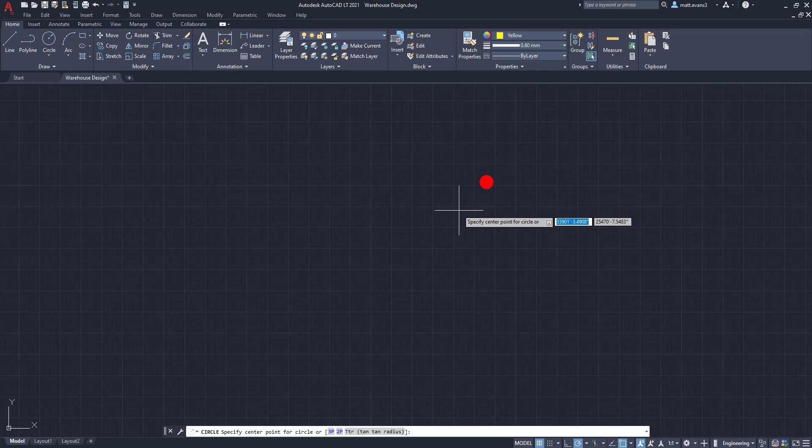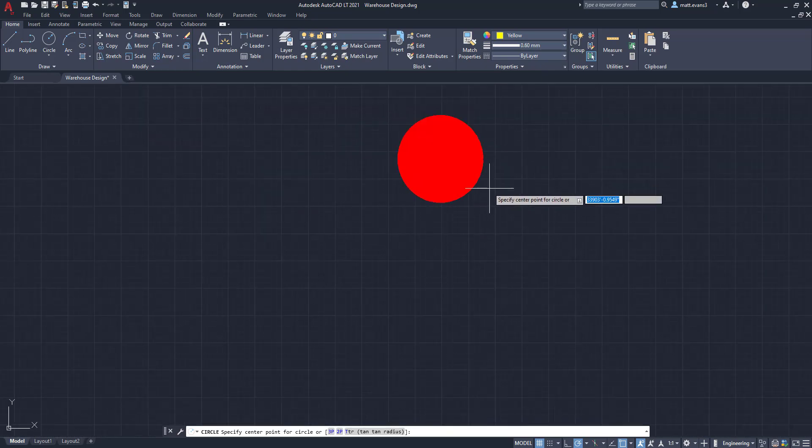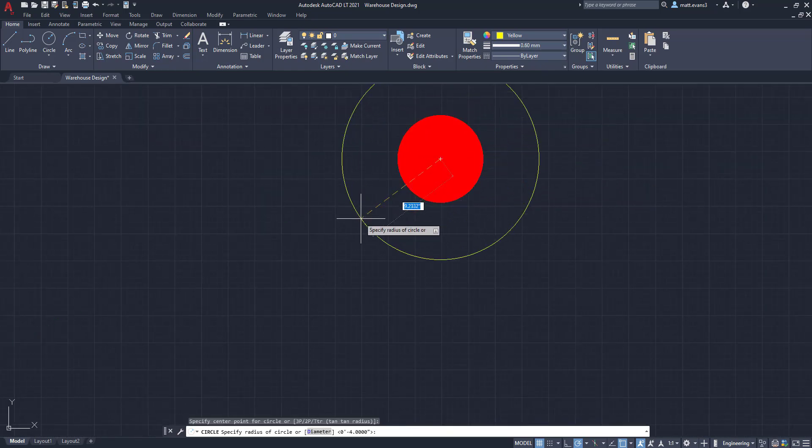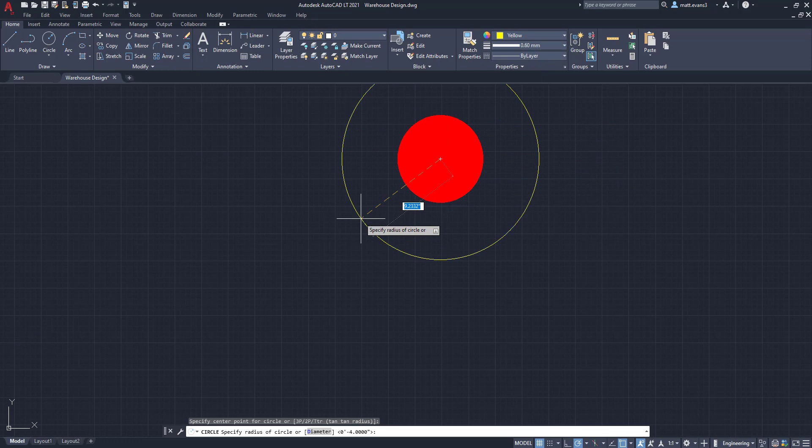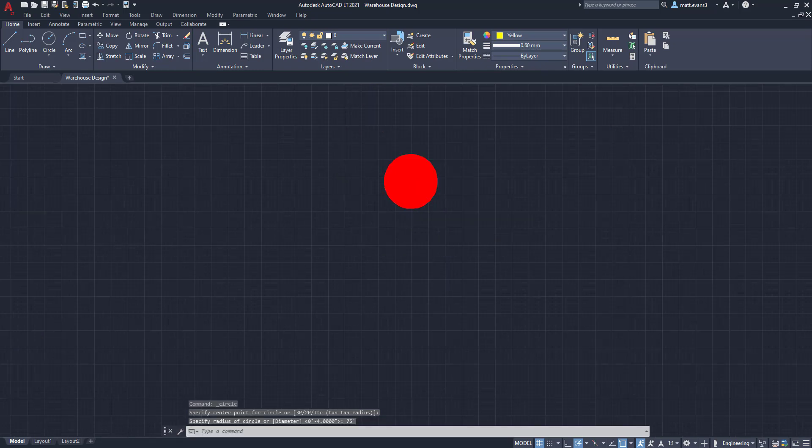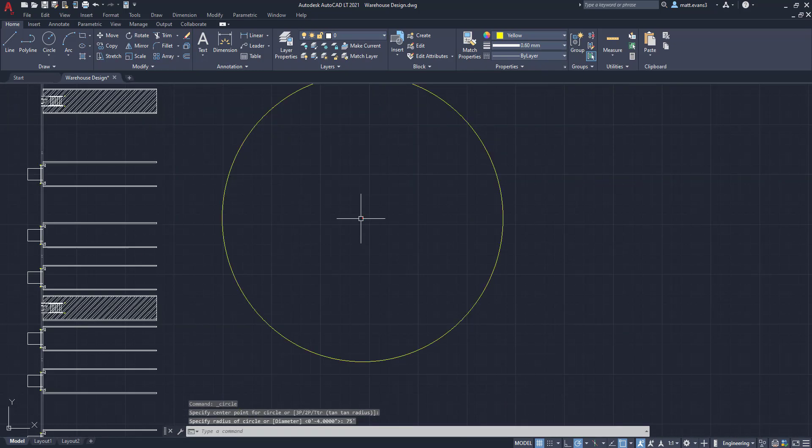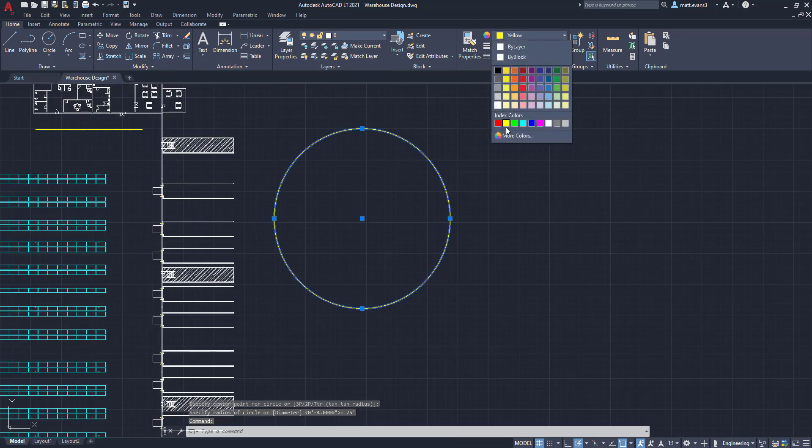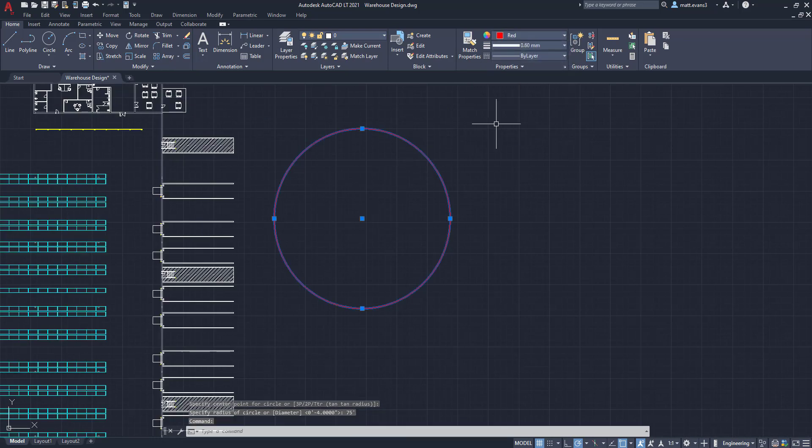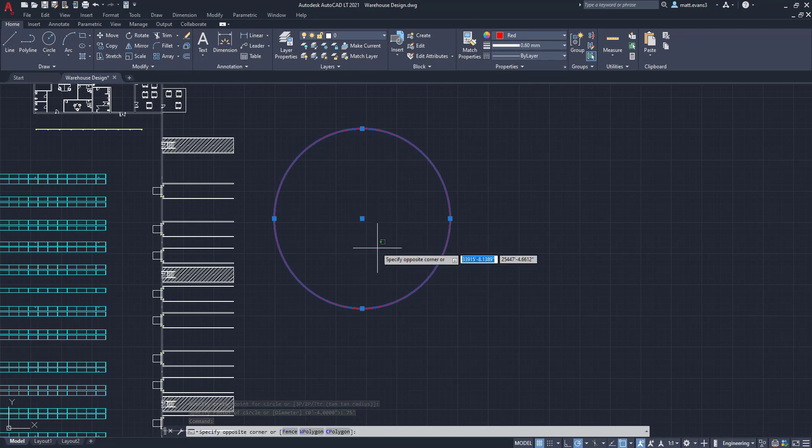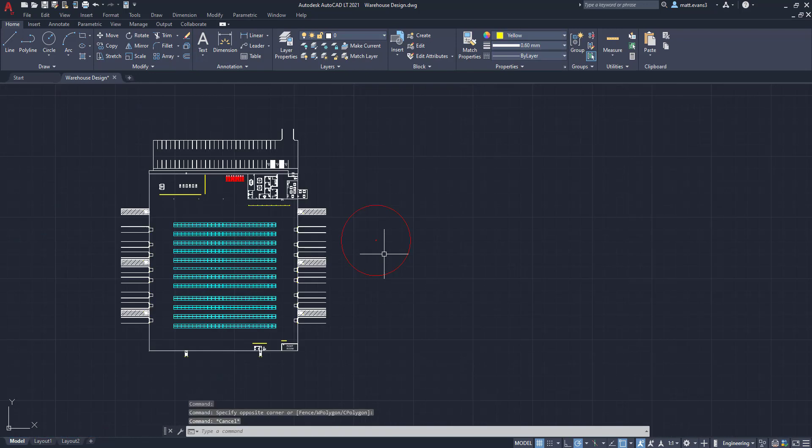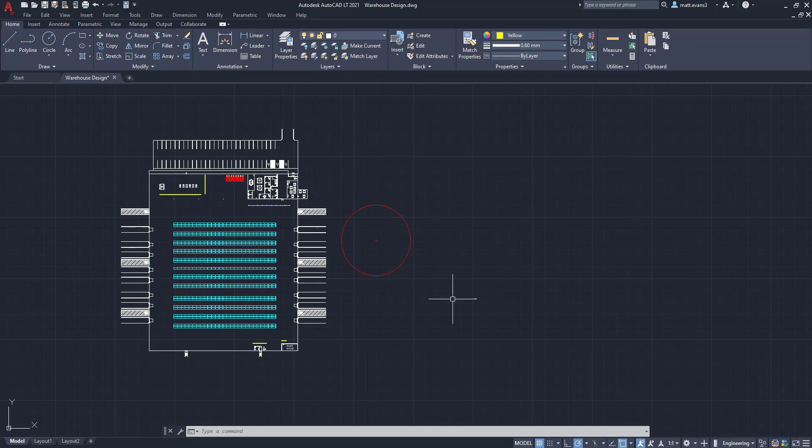We're going to come to the fire extinguisher. And we're going to find the middle of it. And we're going to come out 75 feet. That is the radius. And as you can see here, it's yellow. We're going to actually turn it to red as well. But here now you have a radius for fire extinguishers. What the radius allows you to do is overlap this circle right here to show that it's 75 feet from any given point for the fire extinguisher.